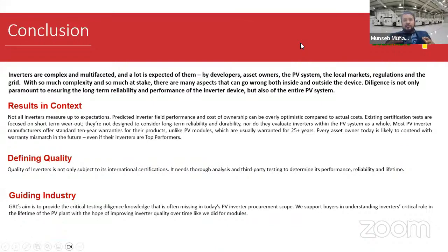So the conclusion that we derive from this presentation is that inverters are complex and multifaceted, and a lot is expected from them by developers, asset owners, the PV system, the local markets, the regulators, and the grid authorities. They're all eyeing inverters with so many expectations, with so much complexity, and so much at stake. So there are things which can go wrong on the inside and outside of the device. So diligence is not only paramount for ensuring the long-term reliability and the performance of the inverter, but you need to consider the optional tests for reliability and the performance of the system.